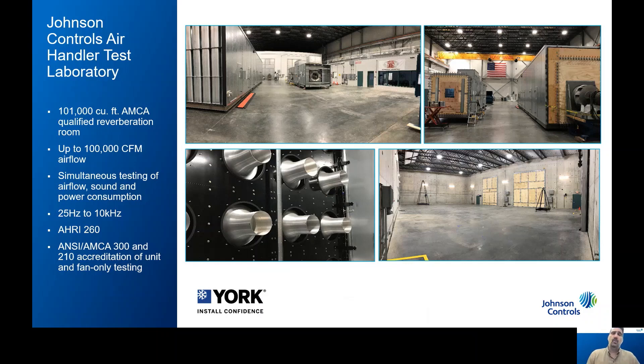As mentioned previously, we were awarded an AHRI performance certificate for 100% success on air performance. This is only possible through extensive design performance testing at our air handling test facility. This lab includes one of the world's largest AMCA-qualified reverberation rooms for acoustical testing. We can simultaneously test flow, sound, and power consumption on units up to 100,000 CFM. It is also an AMCA 300 and 210 accredited test lab. All of our product components, such as fans and motors, go through extensive testing in this lab to ensure customers get the high-performing units that we promised.